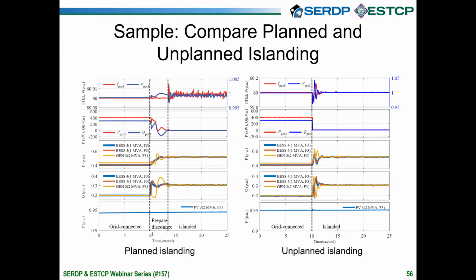So this slide shows another test side by side, better to say two. One of them is a planned islanding. The other one is the unplanned islanding that I showed before in another configuration. The planned islanding, of course, means that we have a forewarning where the utility tells us that the microgrid has to go offline or be disconnected from the main grid, but we have some time to do that. So in that case, we kick in the controller and gradually regulate down the power at the point of interconnect to 0, so that the disconnection can happen. So the left side shows this transient period, what we have time for, because we have a forewarning for this disconnect. And the algorithm kicks in, regulates it down to 0, and stabilizes the microgrid, and then the disconnection happens.